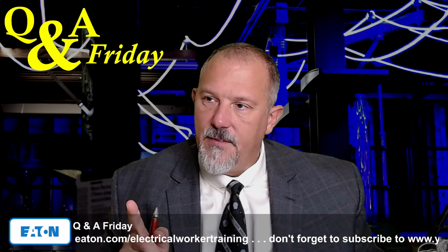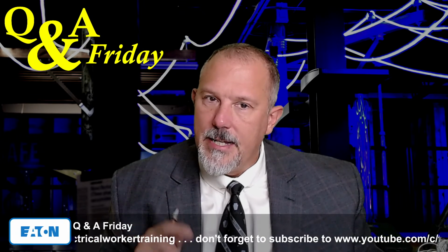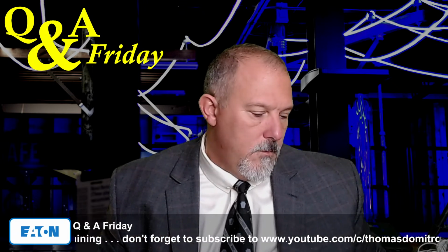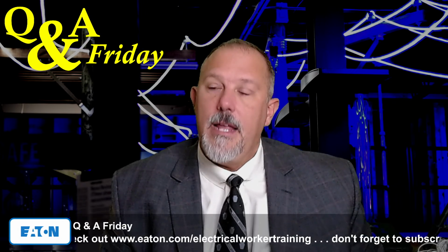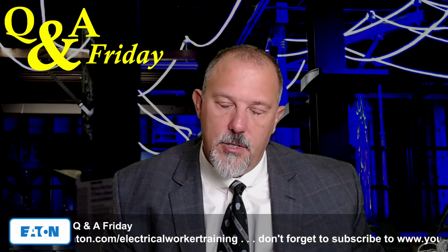In any case, remember we were talking about the feeder rules, about the demand. It was the Q&A from Friday, so that was July 27th. Great job in breaking down the solution in a clear manner. And it was, I believe that 230 does not have an overcurrent protective device reference because it's a service. By definition, if there was an overcurrent protective device, the conductors would become feeders. It is for this reason I'm allowed to run feeders through a building to another building, but I cannot run a service in the same manner. Roger, you are absolutely correct.